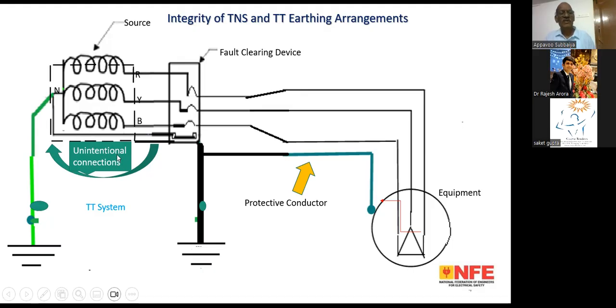Actually, cable armors are not intended to carry the fault current. They are supposed to protect the cable and provide some screening against EMI, the electromagnetic interference. But unfortunately it is resulting in a fault carrying conductor. That's why, in a TT system, whether you adopt TT or TN-S is your choice, but you have to make it.